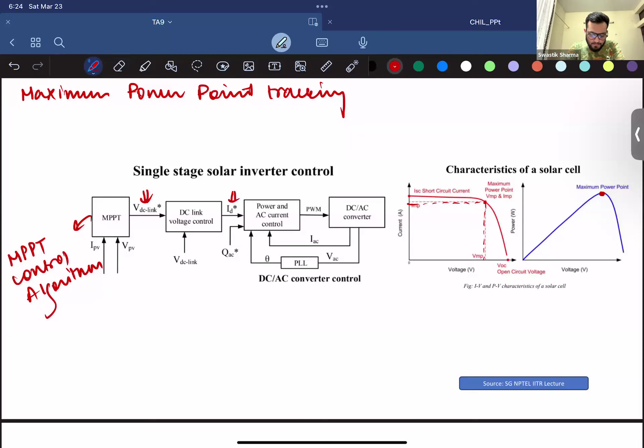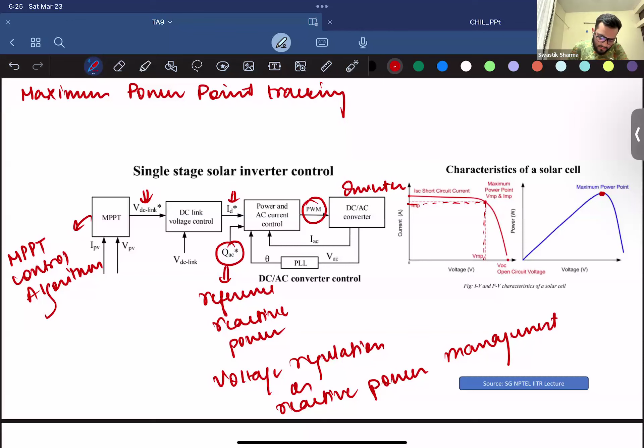Since we want reactive power control from our inverter, what we usually do is, with the AC current control, we also provide a reactive power control, where we give a reference reactive power. So usually we want voltage regulation or reactive power management, and using this control logic, we can provide this management by issuing a reference Q at our own volition.